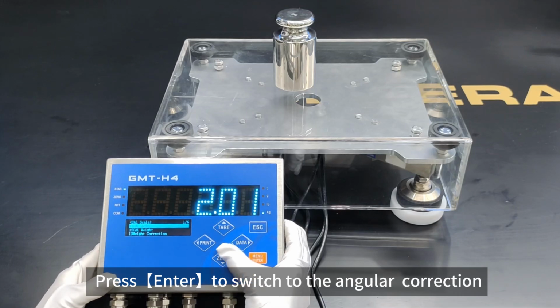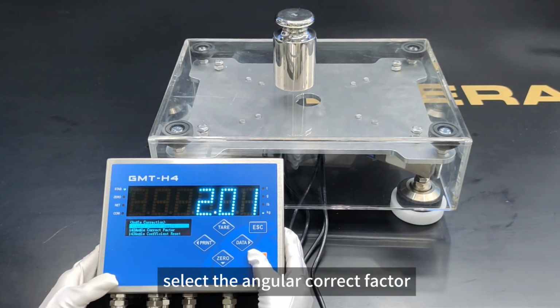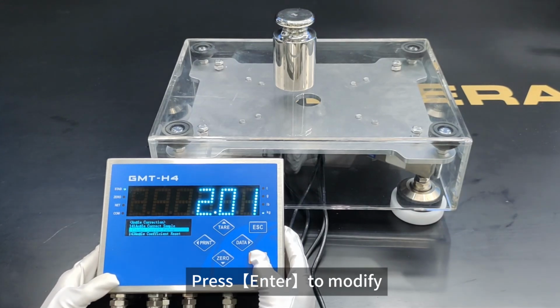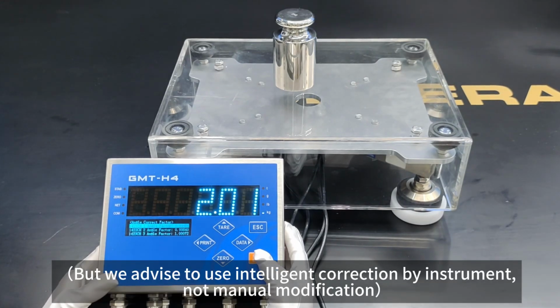Meanwhile, we can set the angular difference coefficient manually. Press Enter to switch to the angular correction. Select the angular correct factor. Press Enter to modify. But we advise using intelligent correction by the instrument, not manual modification.